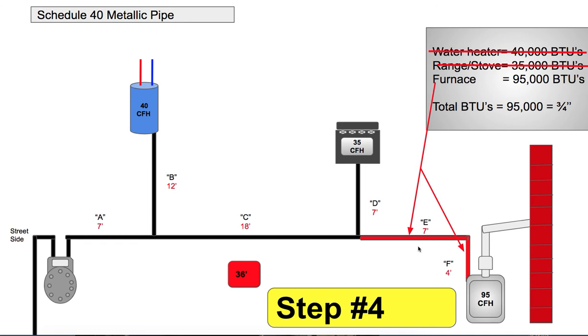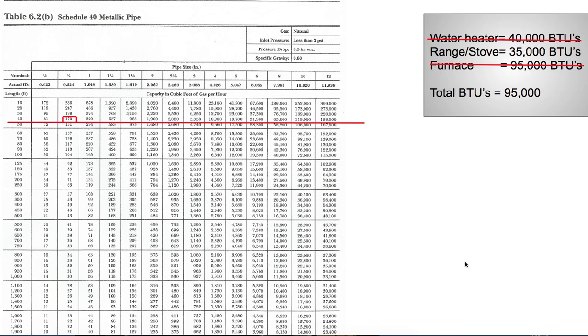The furnace is 95,000 BTUs, and section E of the main — the only load on it is the furnace — that's why they are the same size. Now that doesn't mean that if there's a half-inch gas valve inside the furnace you won't have a half-inch connection at the furnace, but the drop will be 3/4 inch. 95,000 is larger than 81,000, so you go up to the 170,000 row, staying in the 40-foot column — it's 3/4 inch.